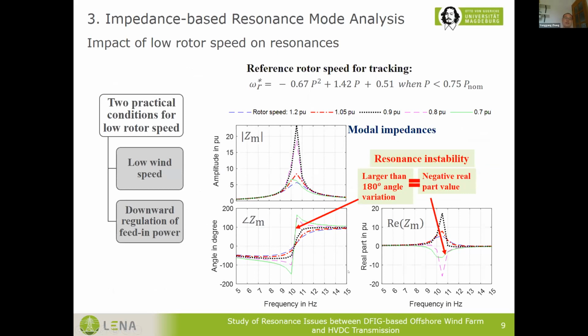This slide presents the impact of low rotor speed on resonances. Two practical conditions for the low rotor speed in offshore wind farm will be the low wind speed or the downward regulation of the wind turbine feed-in power. For the simulated wind turbine, it will maintain 1.2 pu nominal rotor speed when the active power is above 0.75 rated value. Once the wind power drops below this value, the rotor speed will be reduced following this equation.